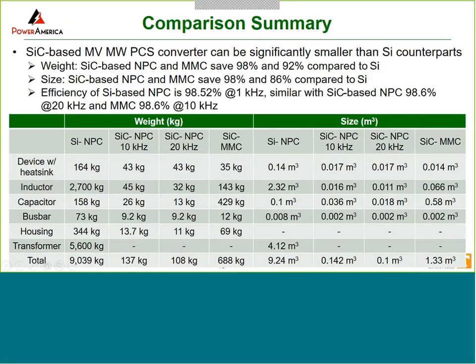So this shows the actual comparison of the 3 different designs, actually 4, because for NPC we have 2 different switching frequencies, and they all are meeting the same converter requirement. And so these are the results in terms of weight and size comparison. We have not done cost, but this is just the weight and size. You can see the huge difference between the silicon carbide and silicon design in terms of weight and size, even without considering the transformer, right? Transformer obviously is heavy and bulky. Even without that transformer, you can still see a huge size and weight reduction by using silicon carbide, mainly because of the switching capability it has and the lower loss.